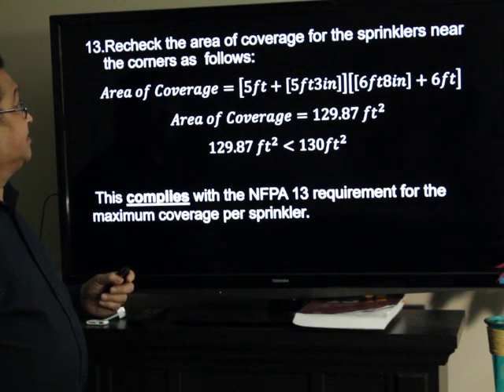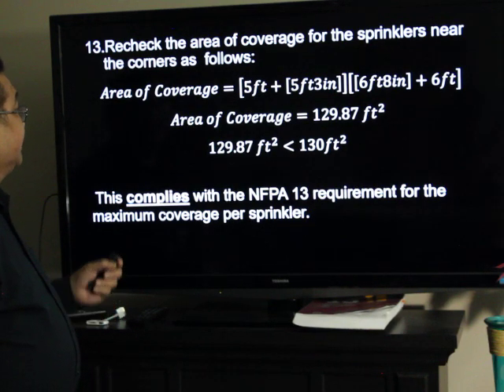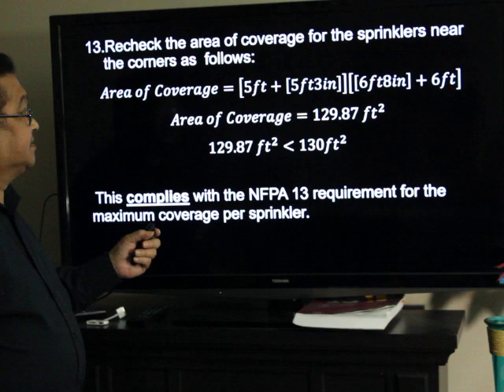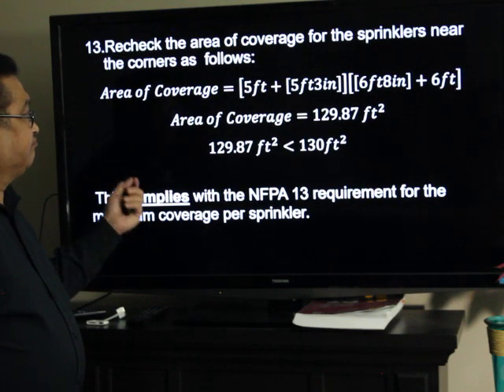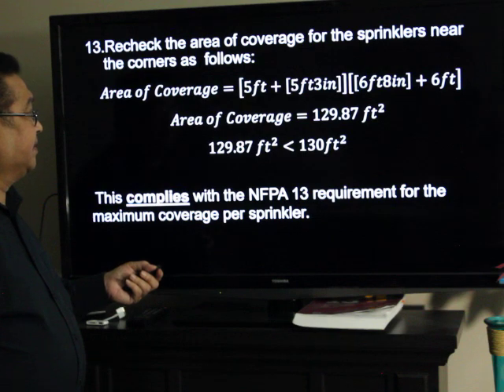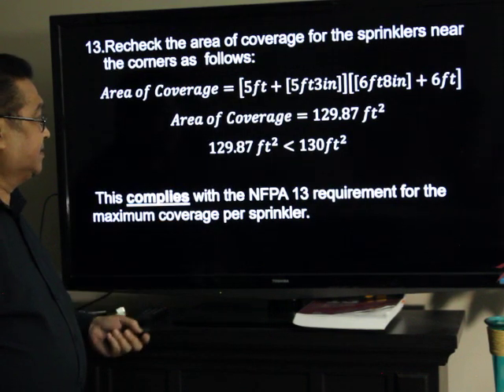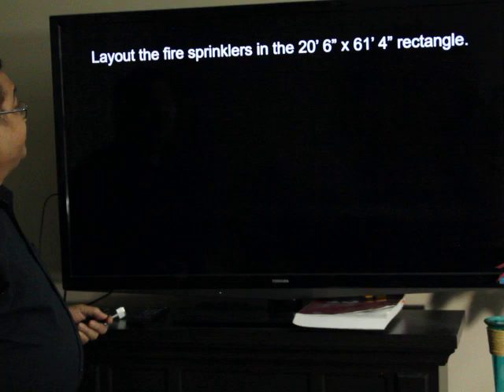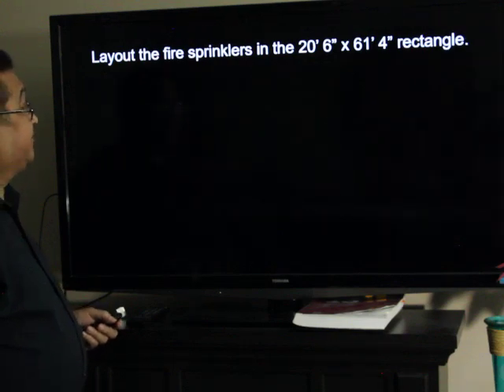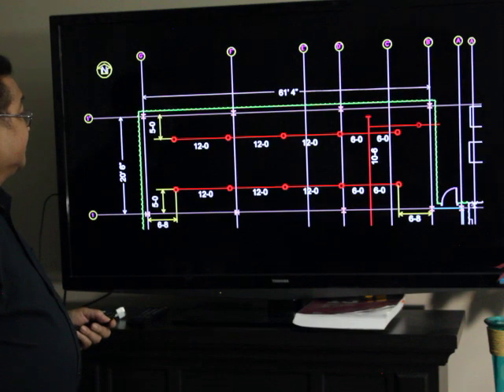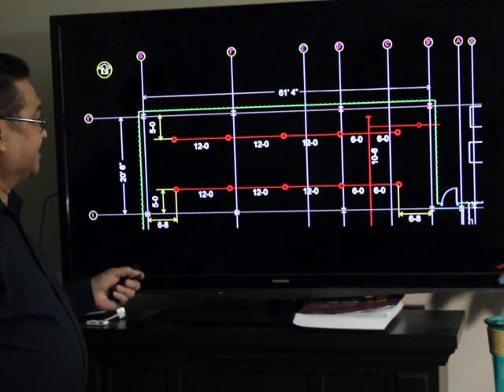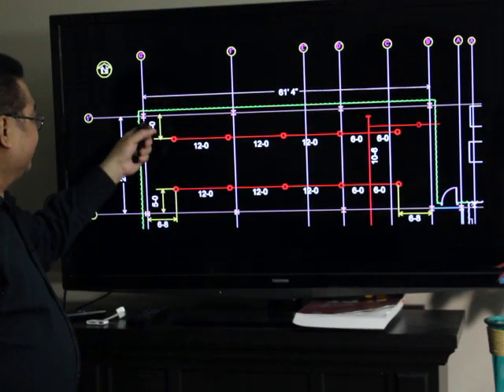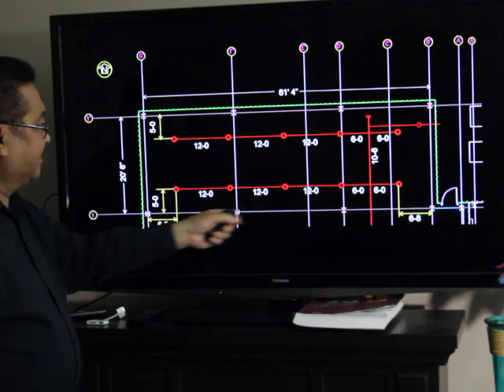Recheck the area of coverage for the sprinklers near the corners as follows. Area of coverage: we have 5 feet plus 5 feet and 3 inches, and 6 feet and 8 inches plus 6 feet. The result will be 129.87 square feet, which is less than 130 square feet — which also complies with the standard. So, lay out the sprinklers in the 20.5 by 61 feet 4 inch rectangle. This will now be your sprinklers. And this will be the branch lines, and this will be the cross main. You have these distances from the wall, from the ends.